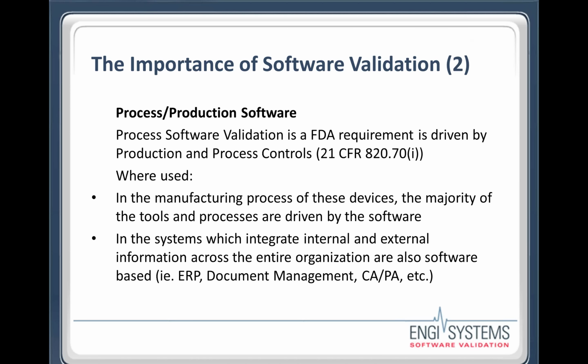The federal regulation that applies to quality system software is found in 21 CFR 820.70(i), Production and Process Controls. It states that all software changes shall be validated before approval and issuance. These validation activities and results shall be documented. Production software is part of the quality system. It's not contained in a medical device.